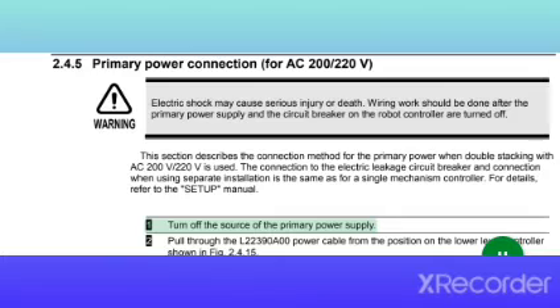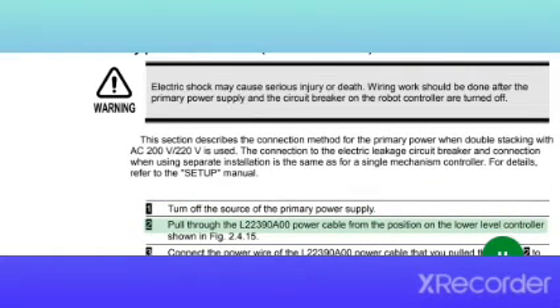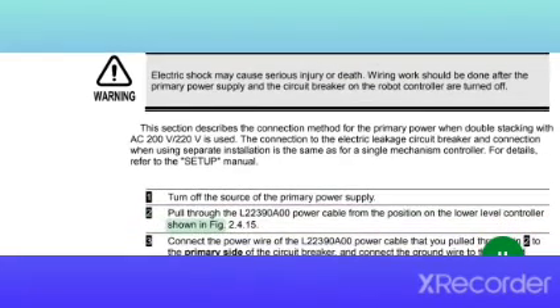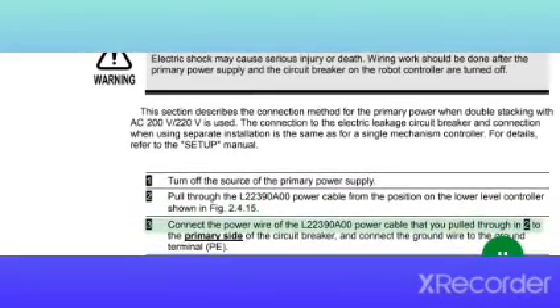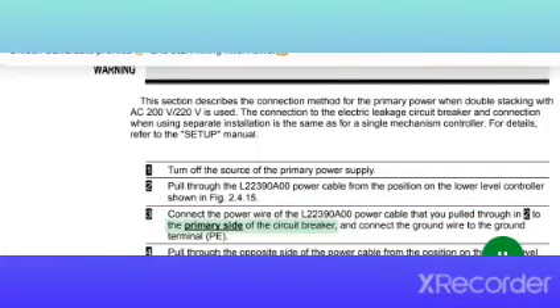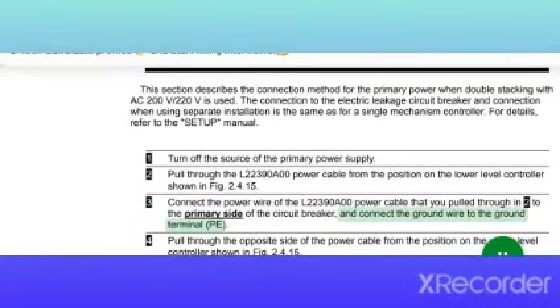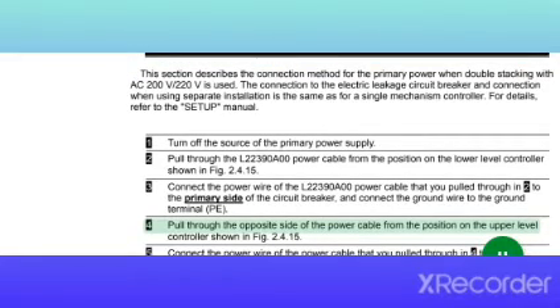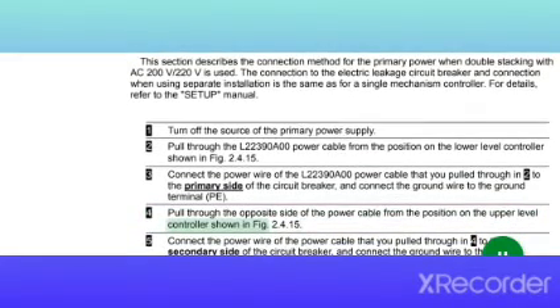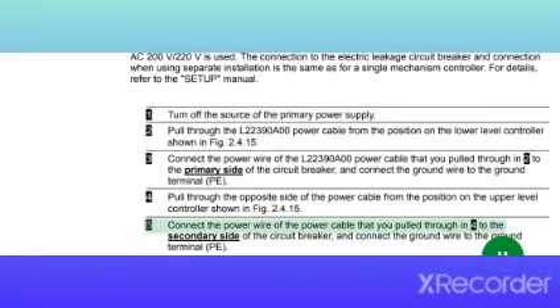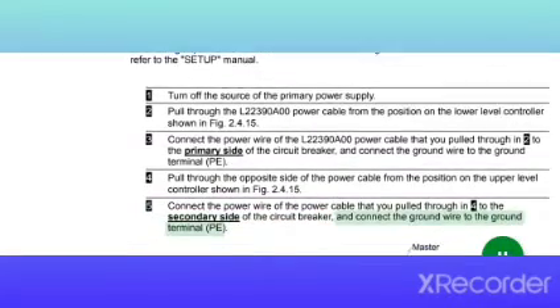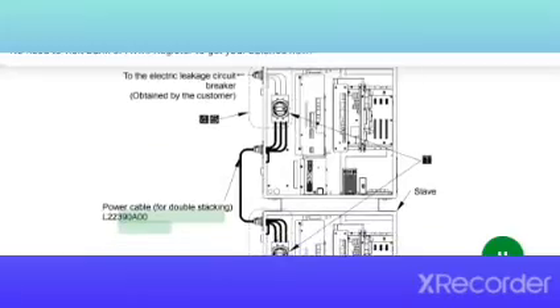1. Turn off the source of the primary power supply. 2. Pull through the L22390A00 power cable from the position on the lower level controller, shown in Fig. 2.4.15. 3. Connect the power wire of the L22390A00 power cable that you pulled through in 2 to the primary side of the circuit breaker, and connect the ground wire to the ground terminal (PE). 4. Pull through the opposite side of the power cable from the position on the upper level controller shown in Fig. 2.4.15. 5. Connect the power wire of the power cable that you pulled through in 4 to the secondary side of the circuit breaker, and connect the ground wire to the ground terminal (PE).